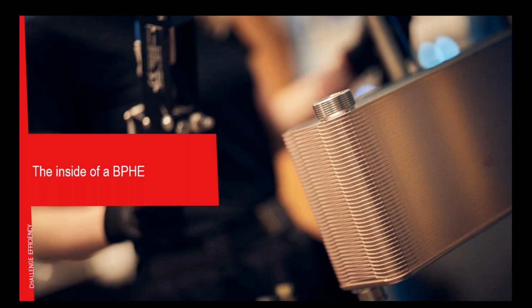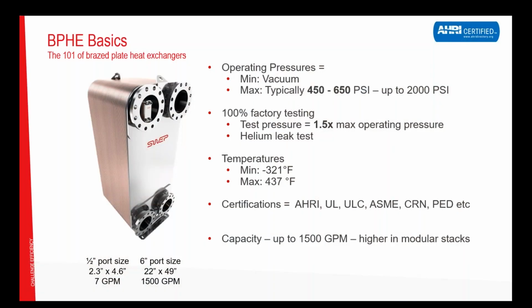Those were the main energy recovery calculations I wanted to show you today, and what part the brazed plate plays in these different systems. I would like now a few minutes to go through what a brazed plate heat exchanger is and what it looks like. If we just take the basics, the smallest brazed plate heat exchanger, BPHE, that SWEP is producing is this one here. It's the size of an iPhone 4, more or less. So it's a palm size heat exchanger with 1/2-inch ports. And the largest one we have is about 4 feet tall with 6-inch ports.